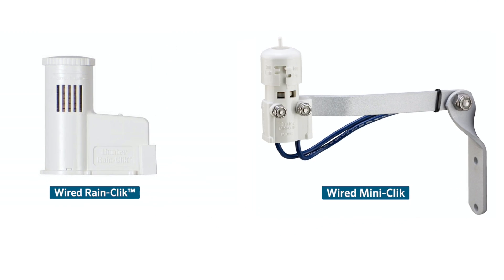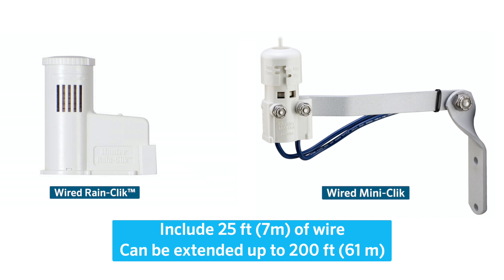Wired Rain-Clik and Mini-Clik Rain Sensors include 25 feet or 7 meters of wire and can be extended up to 200 feet or 61 meters using the same type and gauge of wire that is already attached to the sensor.